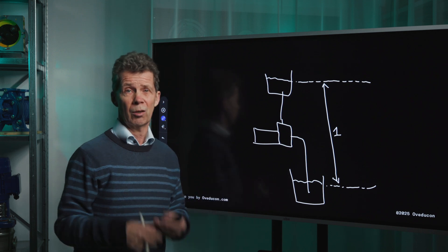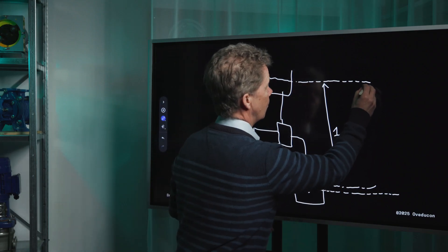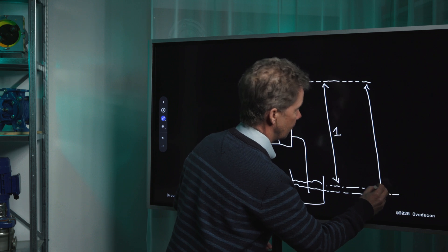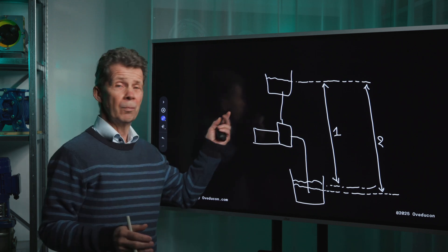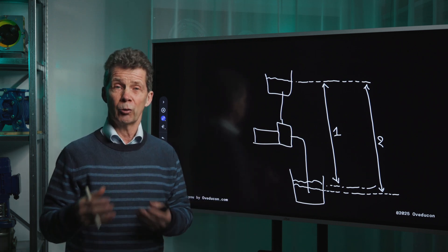Be aware that the medium level can go up and go down. For example, if your medium level in your suction tank goes down, the horizontal line will shift accordingly, and your static head will be larger. So be aware when you calculate your static head — do it for the worst conditions. In this case, that is situation number two. Let's examine a couple of different process layouts to show you how the static head differs for each situation.